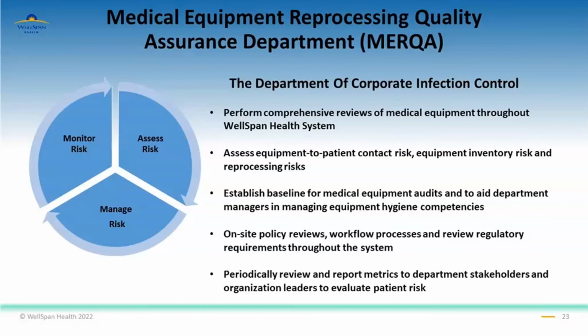Establishing a baseline for medical equipment primarily depends on the MIRA score, which I mentioned, and the end user's cleaning competencies. Our audit frequencies are usually scheduled around 3, 6, and 12-month intervals. Prior to scheduling an on-site process observation, MERQA auditors will review the current manufacturer's instructions for use for all equipment to be audited. Then we'll begin to prepare the process observation document, which will guide the audit from beginning to end. And at its conclusion, the audit will review all areas included in the equipment audit, and it will include the manager and the frontline staff who performed the cleaning and disinfection of that equipment as part of the audit process.